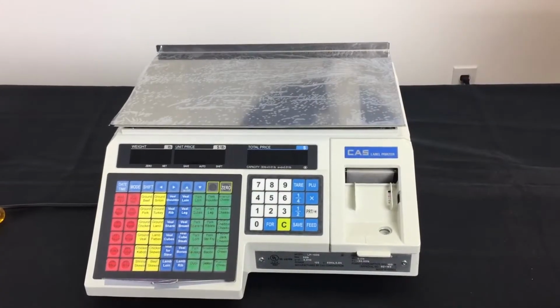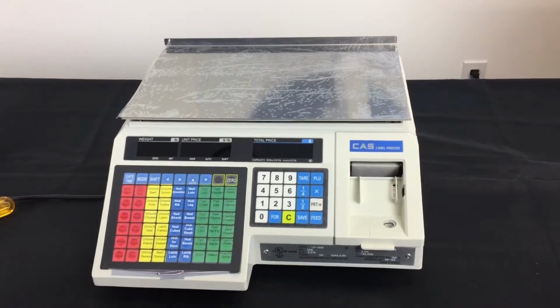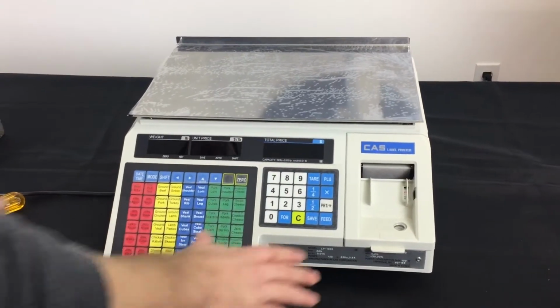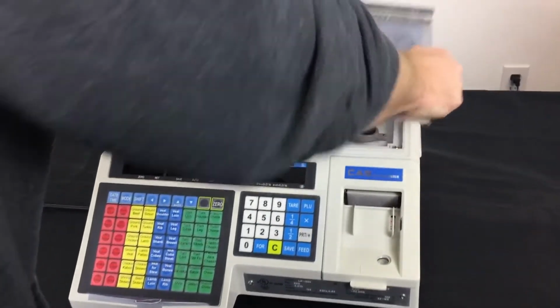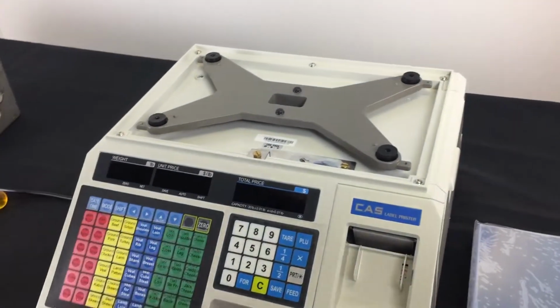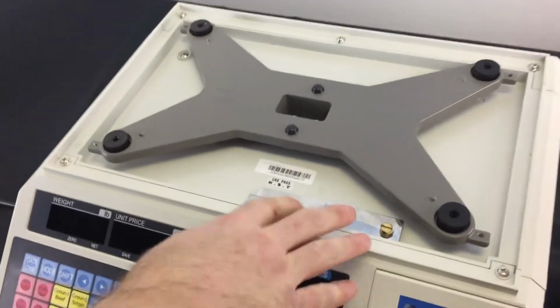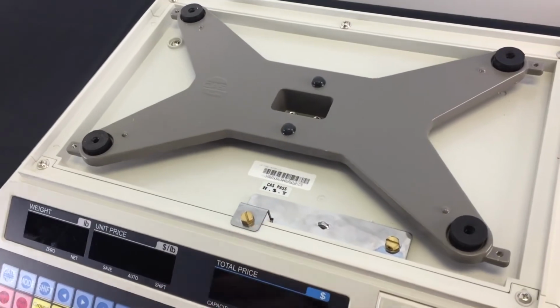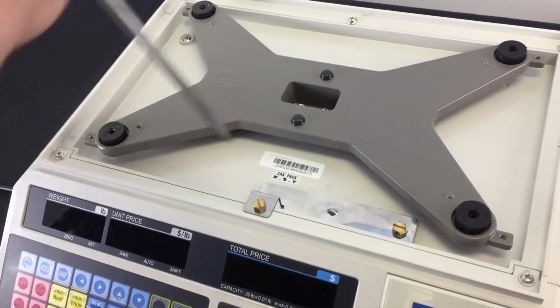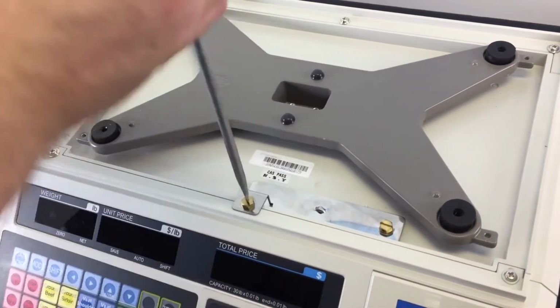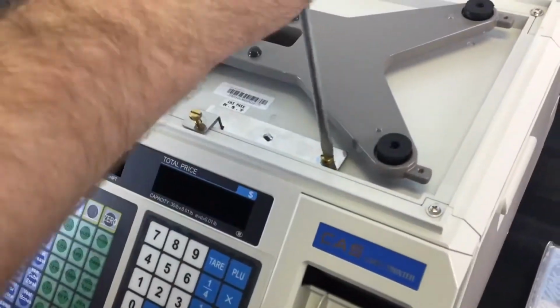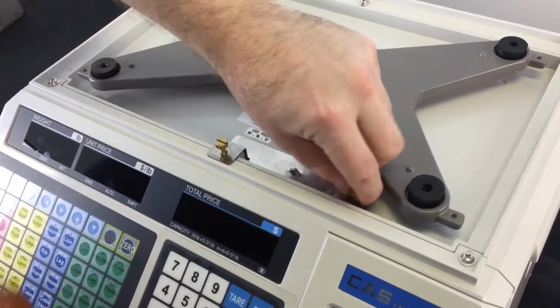This is the calibration process for the LP1000N. Now, in order to start the process, first thing you want to do is go ahead and remove the platter from the scale in order to have access to your calibration plate with 2 sealing bolts. You're going to need a flathead screwdriver in order to go ahead and remove these sealing bolts from the top of the scale. So after you screw these out, you'll have access to your calibration port.